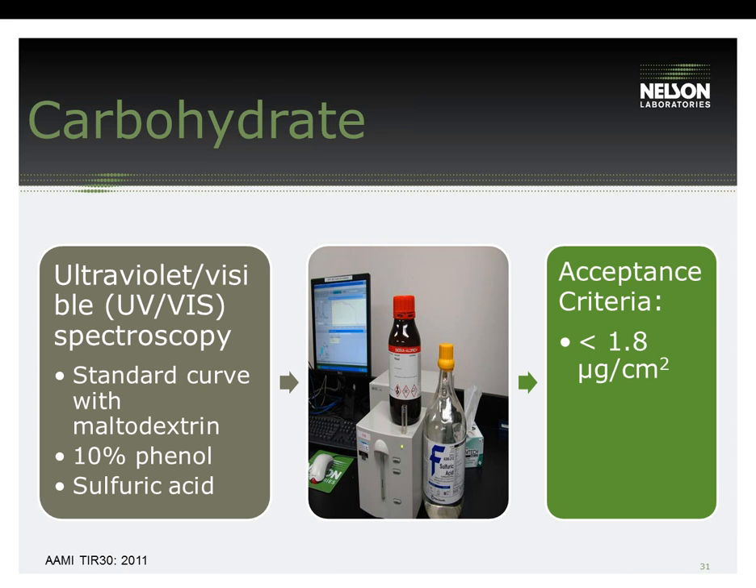Carbohydrate analysis is usually performed if biofilm residues are a concern and if you are interested in evaluating how much carbon is left on the device after reprocessing. Carbohydrate is detected using a phenol-sulfuric acid test method, using a standard curve with maltodextrin and a UV-Vis spectrophotometer at a wavelength of 489 nanometers to detect the level of carbohydrate in the extract collected after reprocessing. The acceptance criteria outlined in TIR-30 for carbohydrates is less than 1.8 micrograms per centimeter squared.